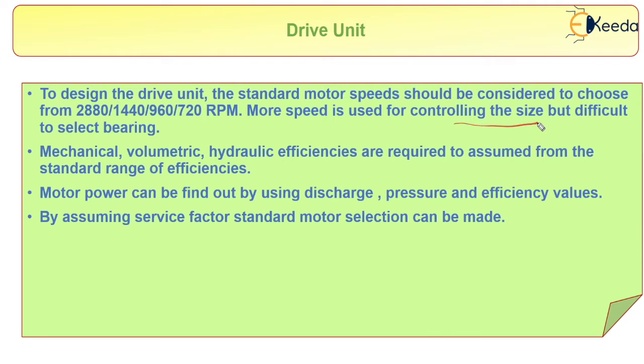Mechanical, volumetric, and hydraulic efficiencies are required to be assumed from the standard range of efficiencies. The motor power can be found out by using discharge, pressure, and efficiency values. By assuming a service factor, the standard motor selection can be done.